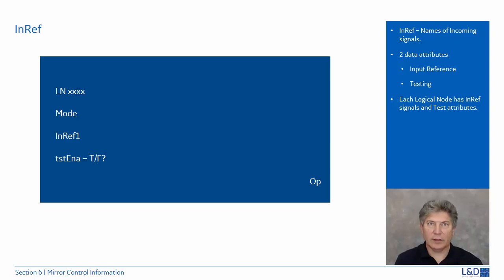Next we'll look at InRef. To provide test inputs, Edition 2 supports the naming of incoming signals in a special reference data object at each logical node known as InRef. These data objects are broken down to two data attributes: one is a reference to the object normally used as an input and the other is a reference to the data object used for testing.